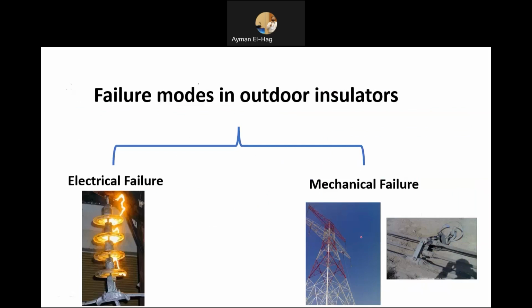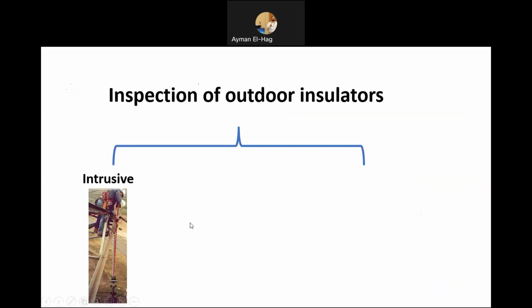And you can see here, this is an example of a failure of non-ceramic insulators at 400 kV, and this is a bundle of four conductor overhead lines that has actually fallen on the ground. So these are very serious consequences whenever there is a failure of the insulators, either electrical or mechanical failure. So it's very important to inspect the insulators to make sure that they are safe from these failures.